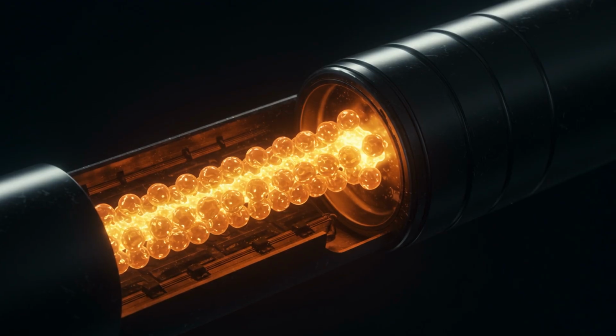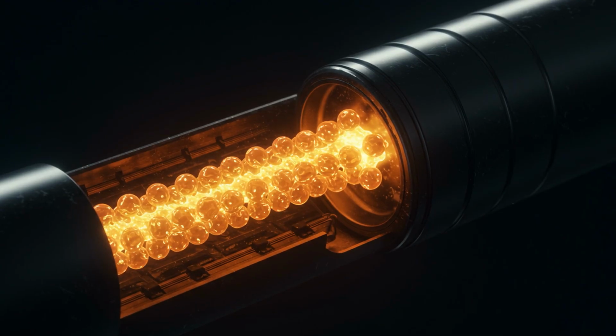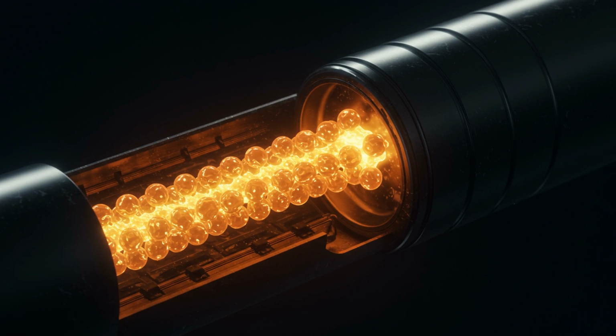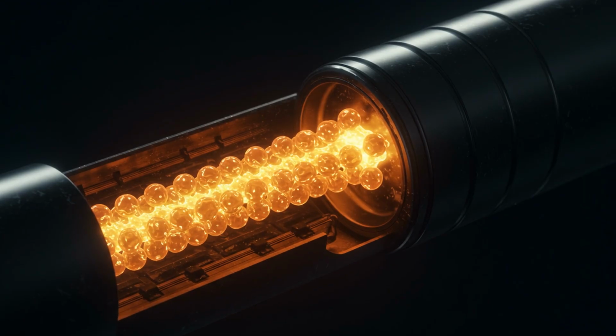When the lithium anode meets the iodine cathode, a layer of lithium iodide forms between them. This layer acts as the electrolyte. And here is the engineering magic. As the battery is used, the layer naturally grows, increasing internal resistance and creating a predictable, gradual voltage drop. This allows doctors to predict exactly, down to the month, when the device will need replacement, years in advance.